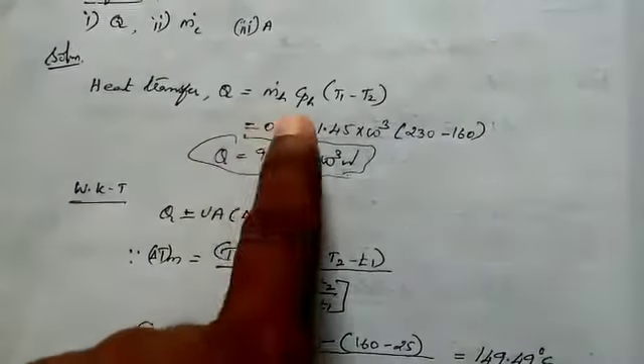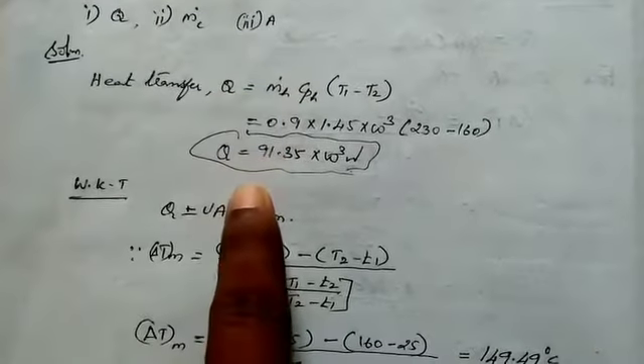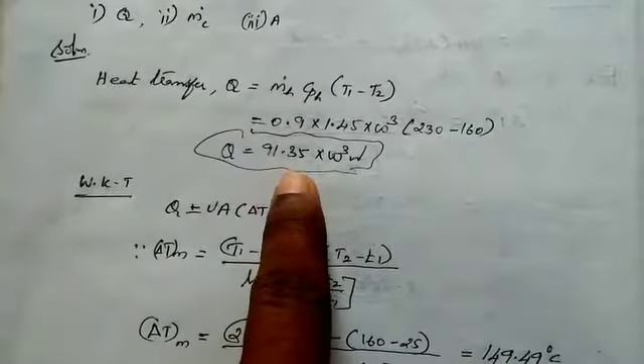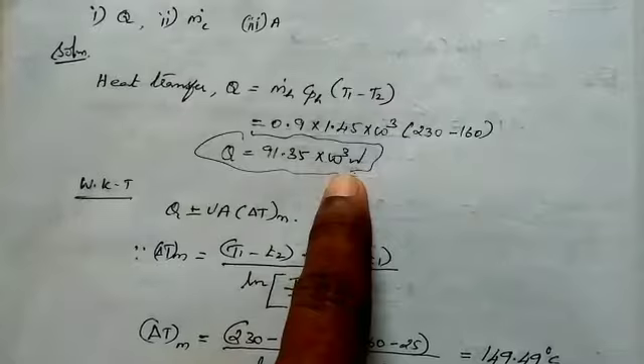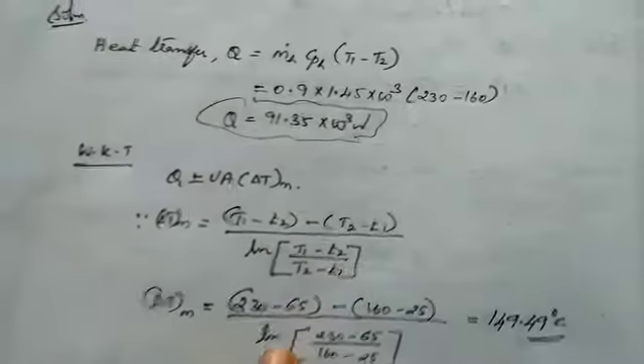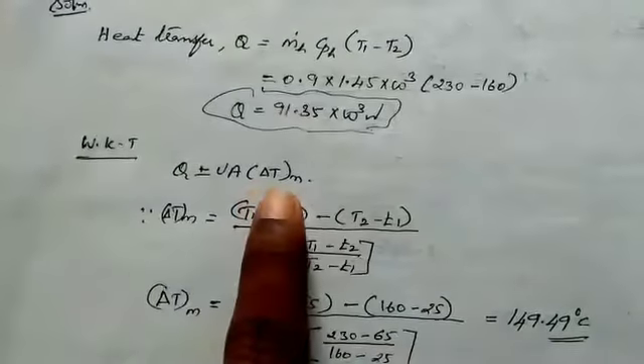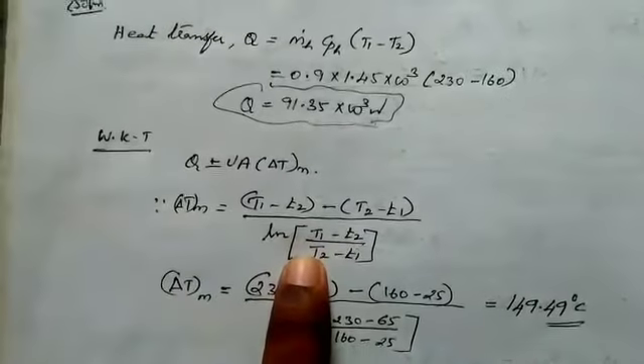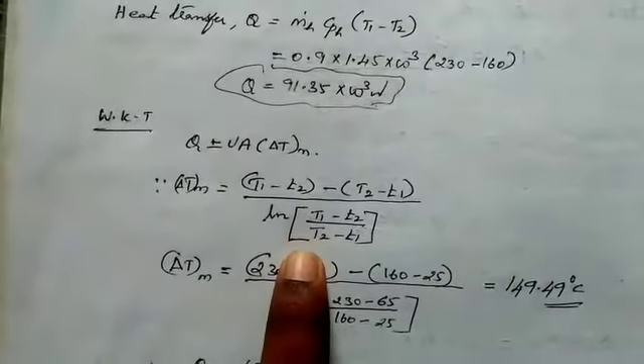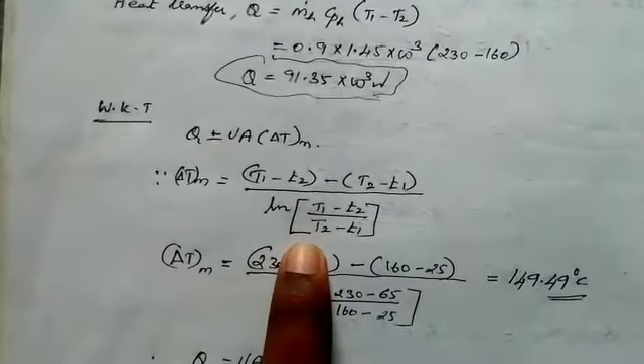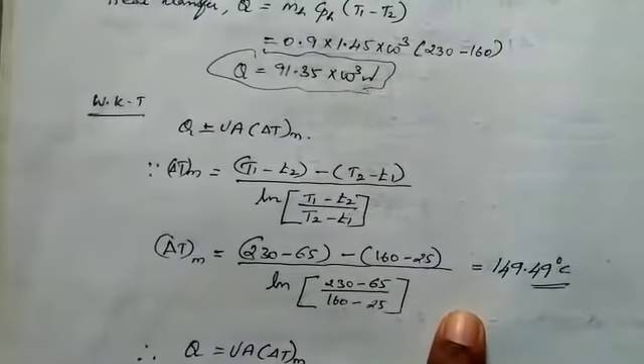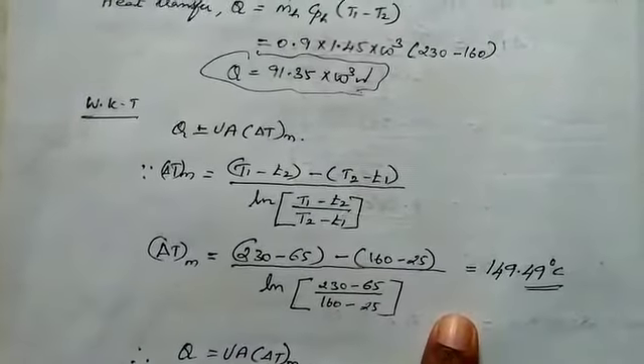We calculate QH. The rate of heat transfer QH = 0.9 × 1450 × (230 - 160) = 91,350 Watts. For area, Q = U × A × delta Tlm. For counter flow, delta Tlm = 149.49 degree Celsius.